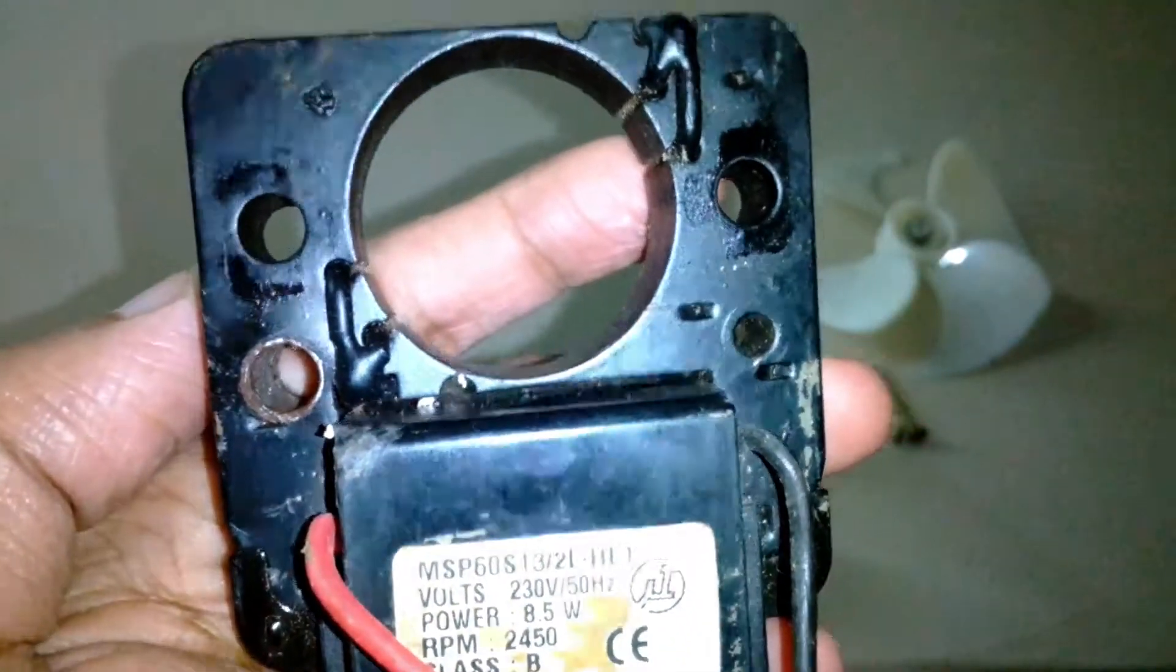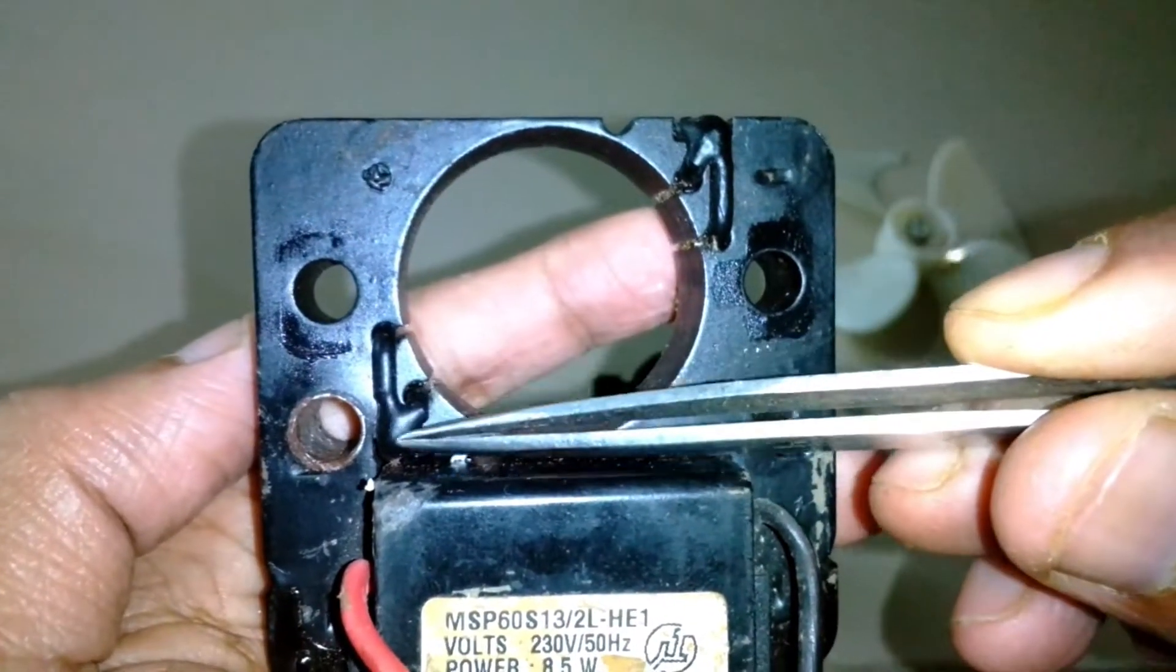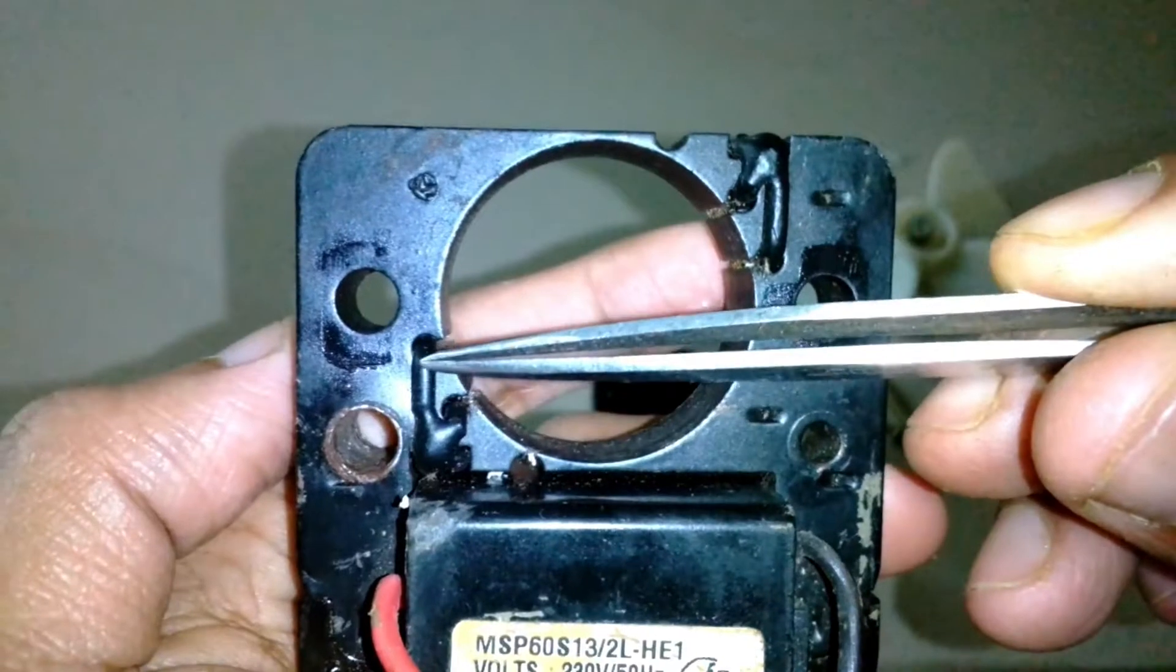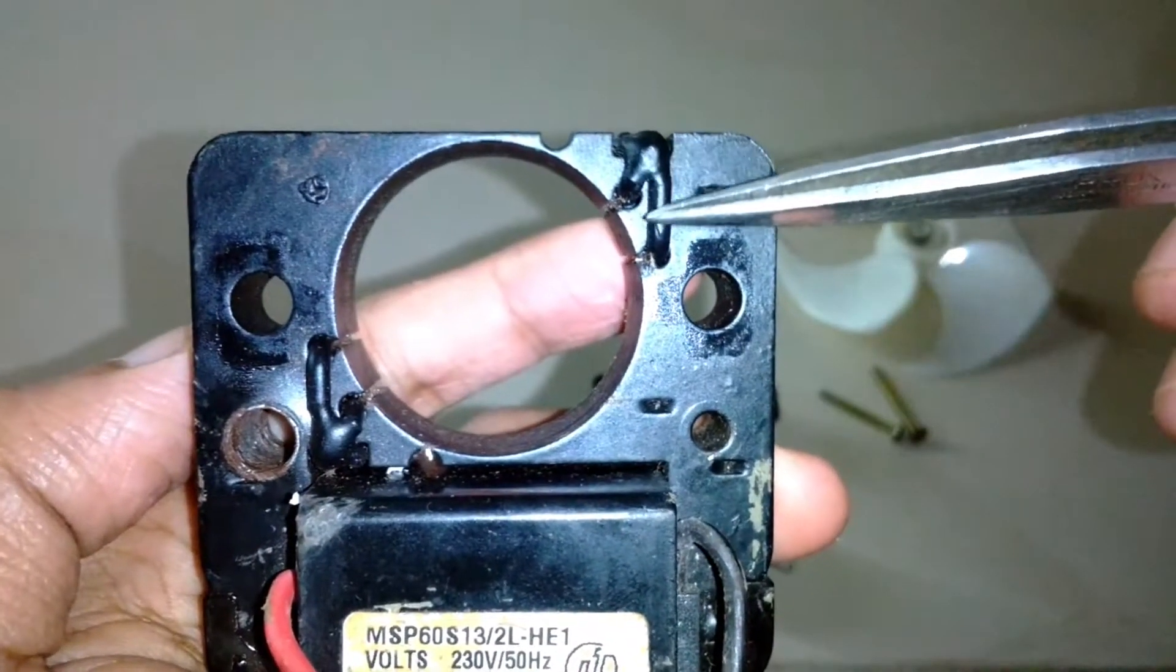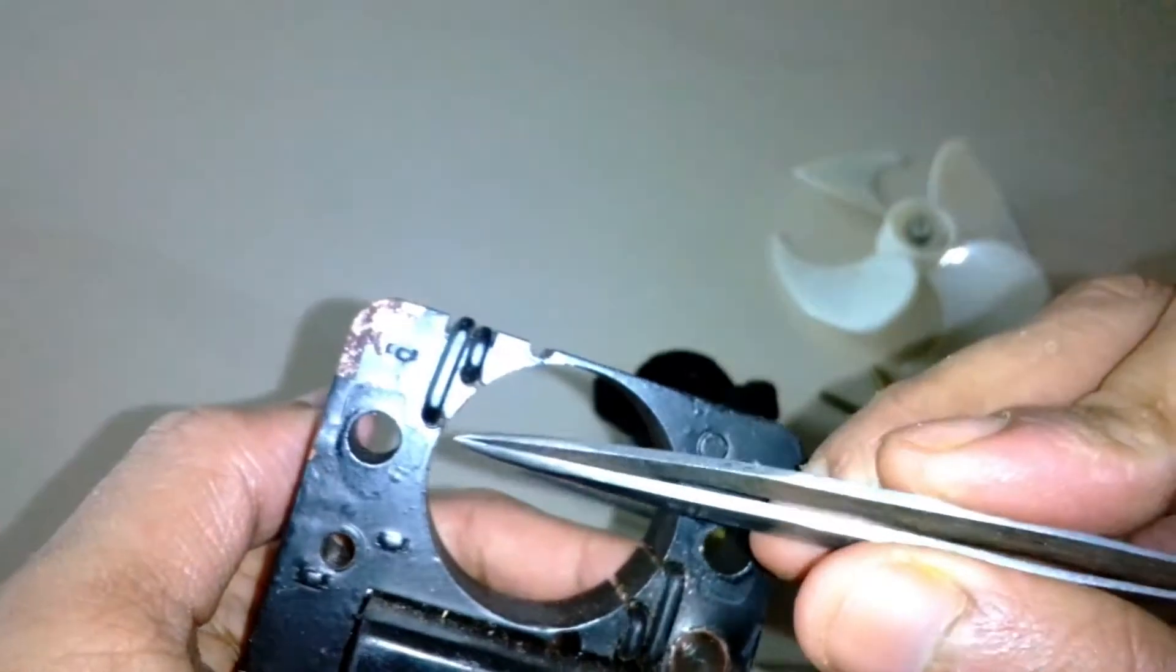How the shaded pole induction motor works: it works due to these rings over here. You can see these are copper rings here. They're actually painted black but they're purely made out of copper and they act as a solid coil. They're shorted out in both sides.